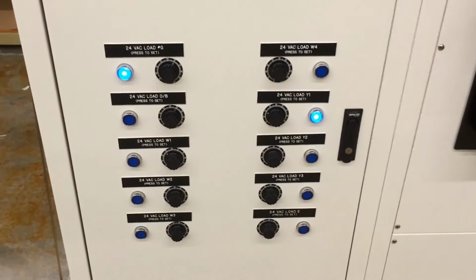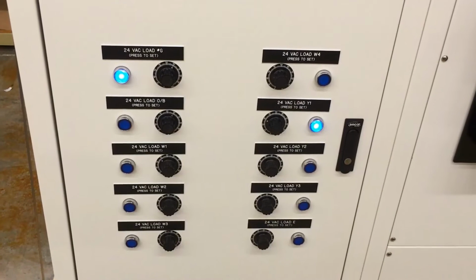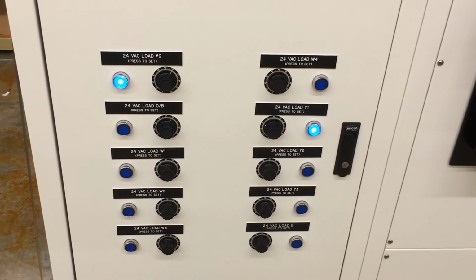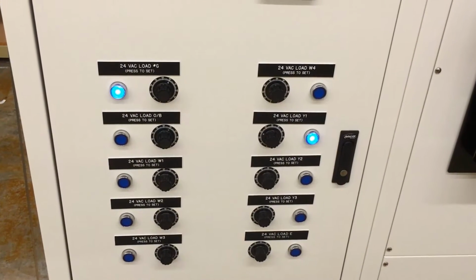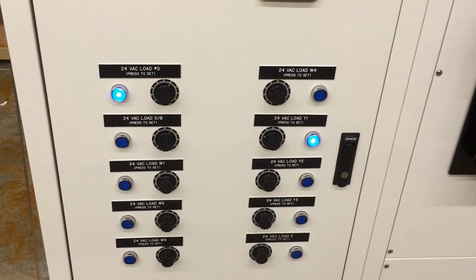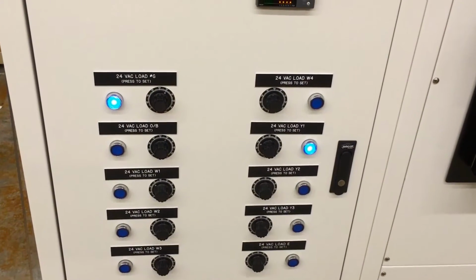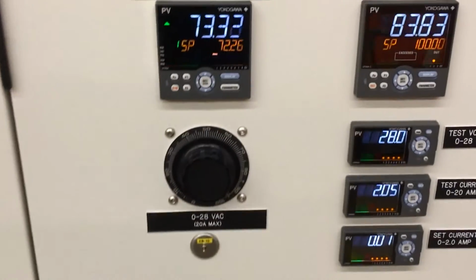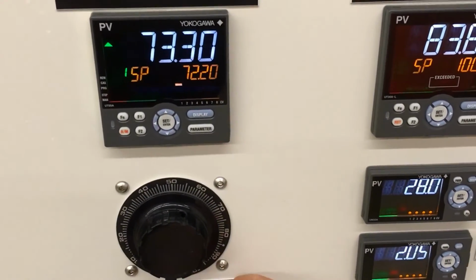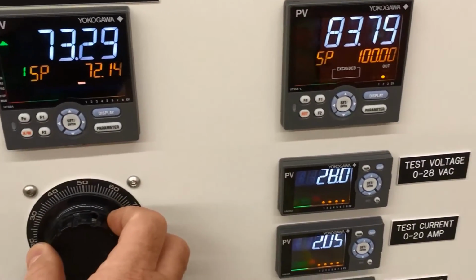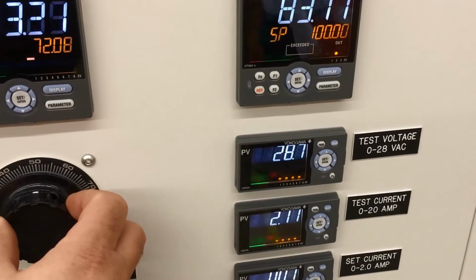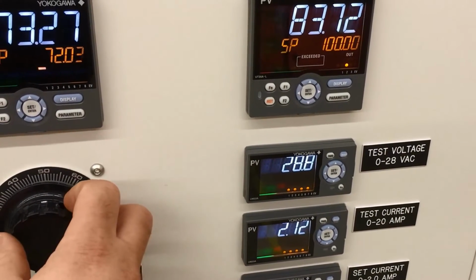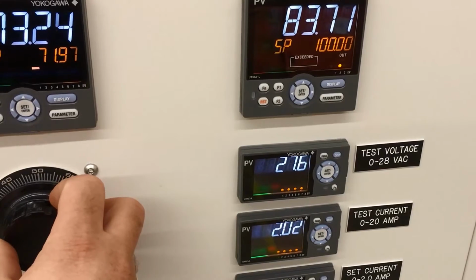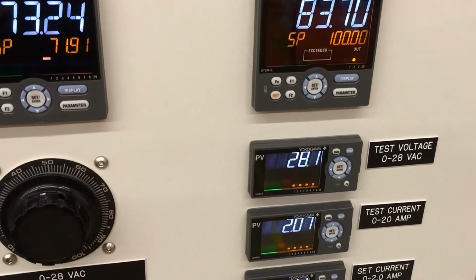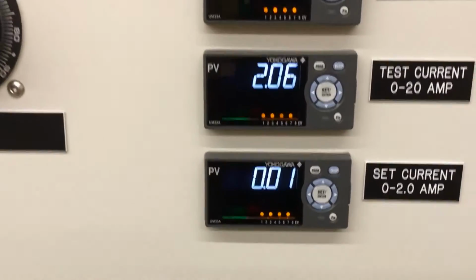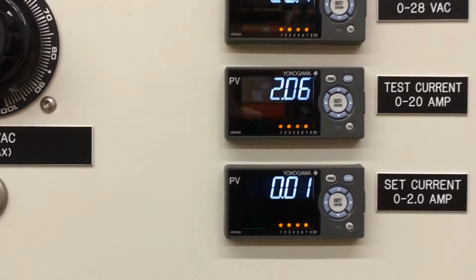For each of the thermostat loads, you can individually set the load current of each load, such as the fan circuit, the heat loads, or the cooling contactors. You can adjust the test voltage that's actually running the thermostat. We're going to keep it around 28. And this is the total current passing through the thermostat right now.